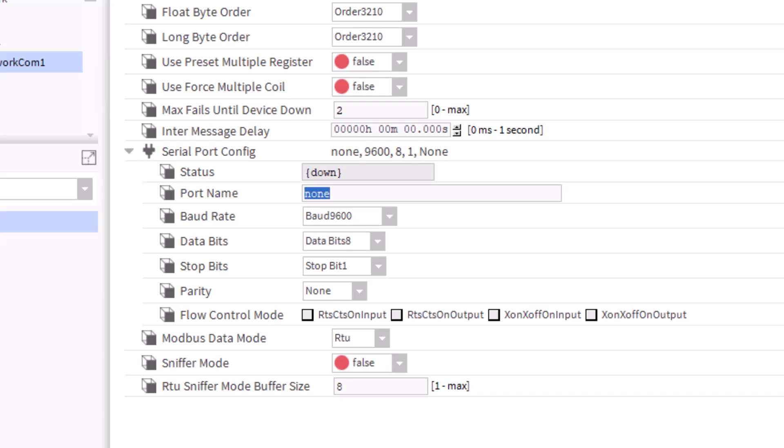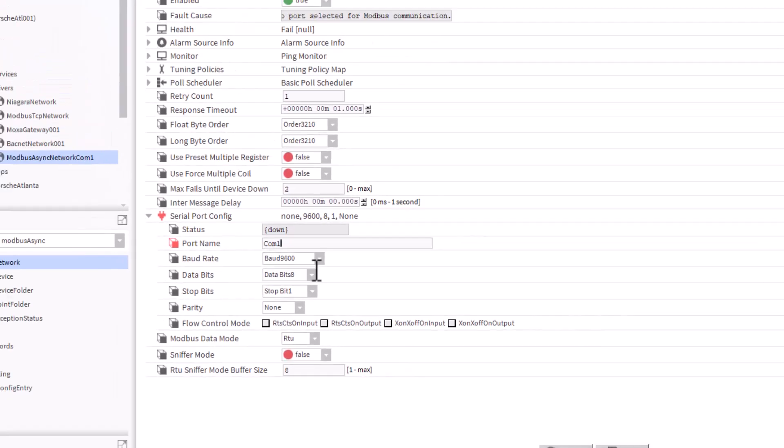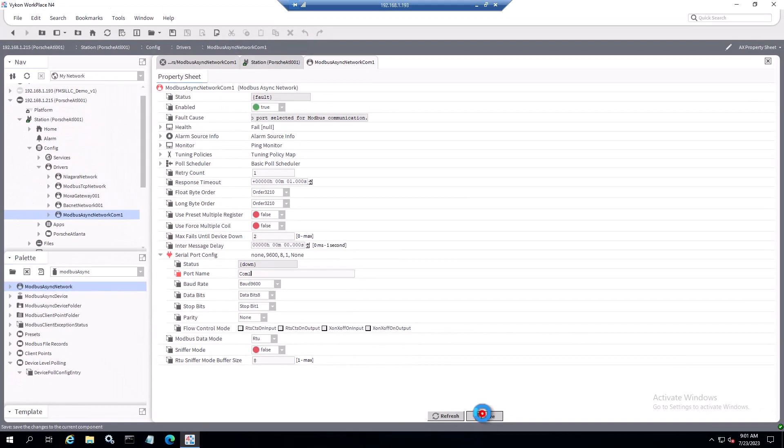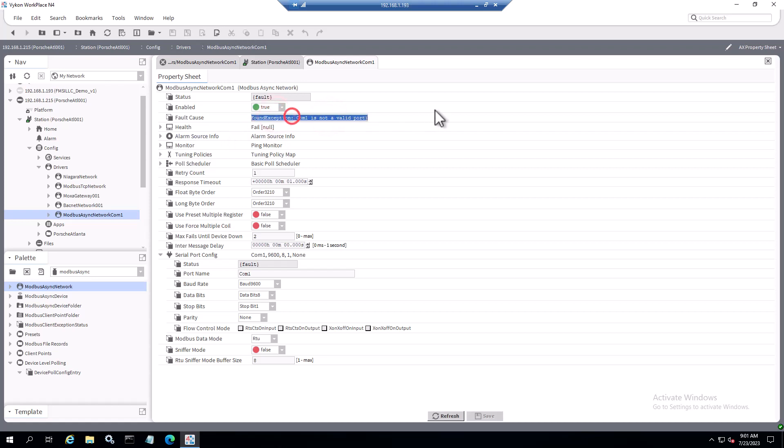Here we just want to call it that COM port name, and this is case sensitive. If I was to do capital C, lowercase o m, digit 1 and then save it, we're going to get a different message saying could not enable Modbus found exception com1 is not a valid port. In order to fix it, we just want to use all uppercase: COM, digit 1.